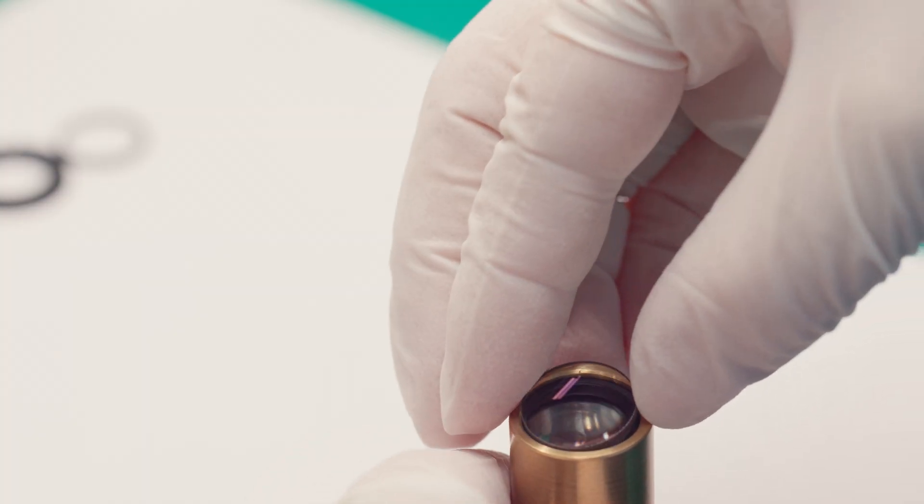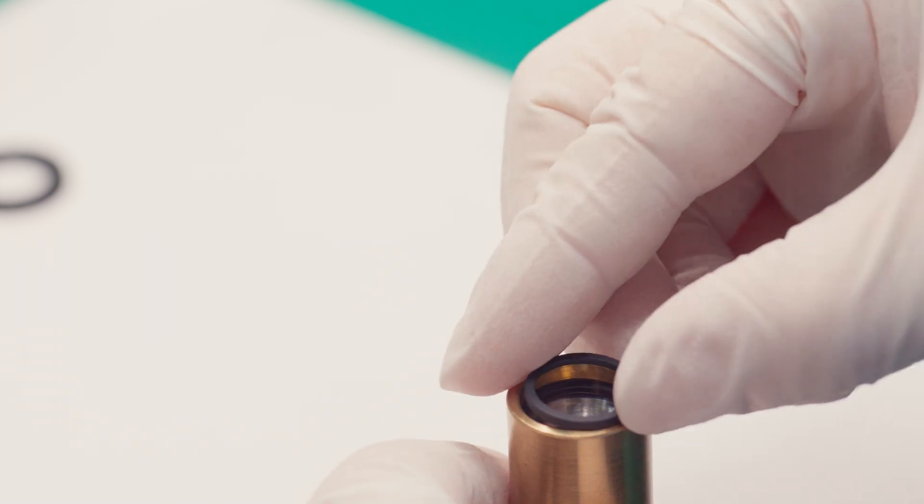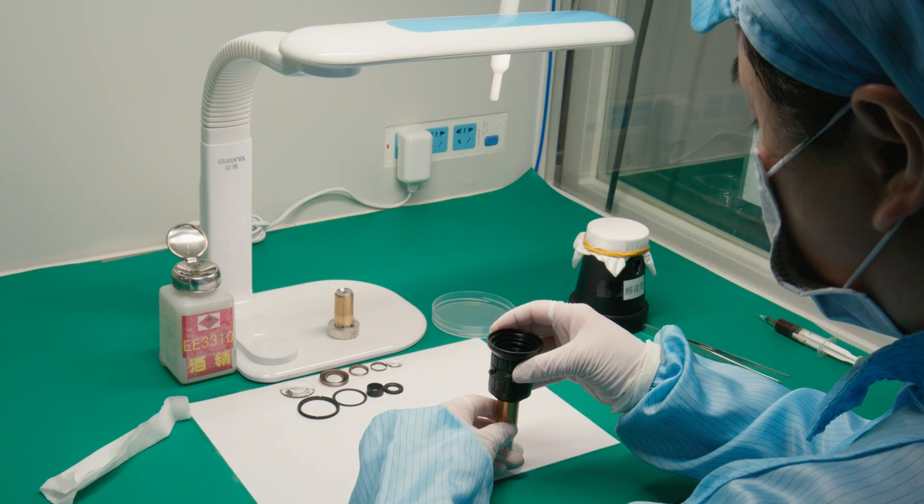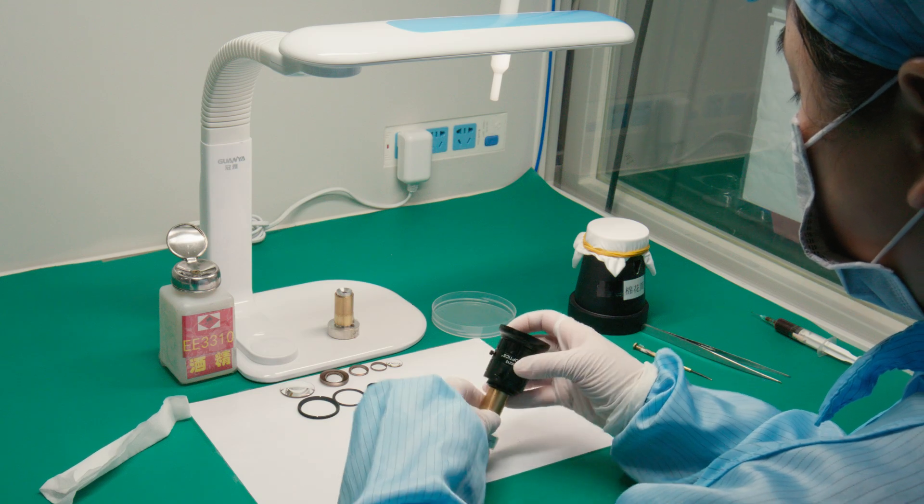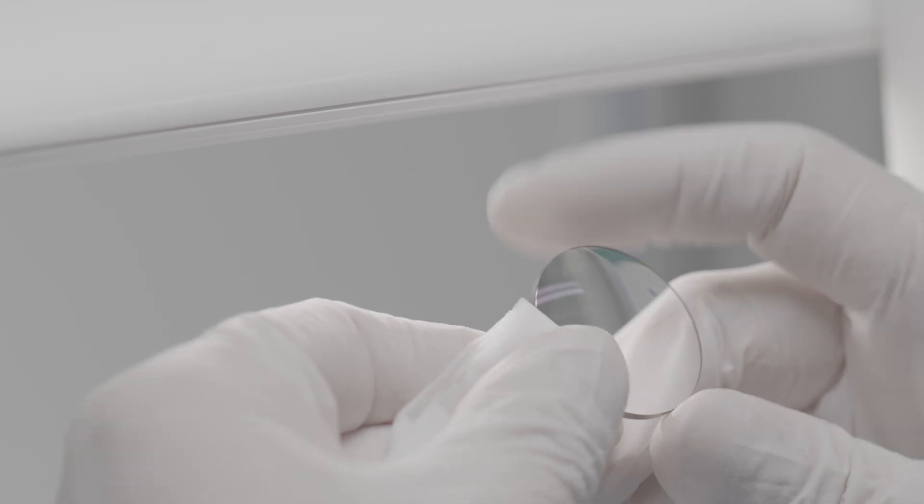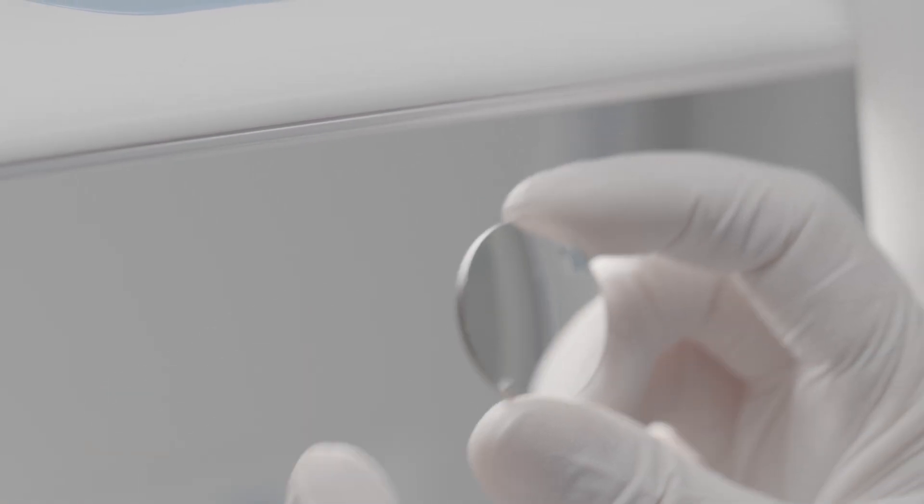Carefully designed spacers are placed in between lens elements to ensure proper lens positioning. Every lens element must be carefully cleaned and inspected before it's assembled.